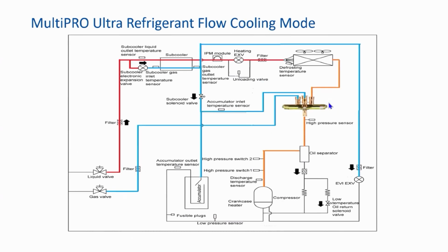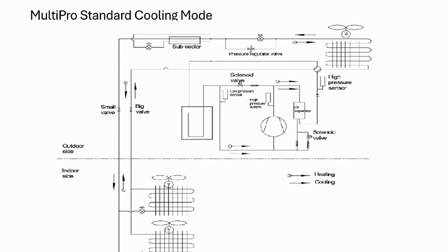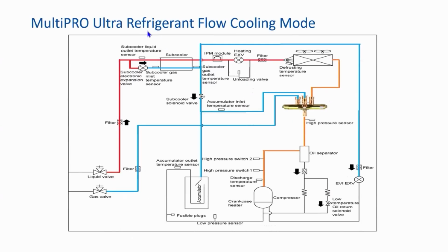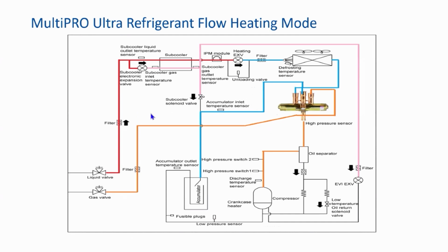And if I go back in my piping diagram, this is the way GREE does them. They just have this little circle up here, which to me is a little more confusing than it is when I actually change up the diagram. So, I mean, this is their diagram. All I did was, and had this put in the service manual, all we did was take out their little circle and made an actual reversing valve. We didn't change the piping at all. And the same with heating mode. Just kind of showing your whole flow through and highlighting it, making it a little easier to read.